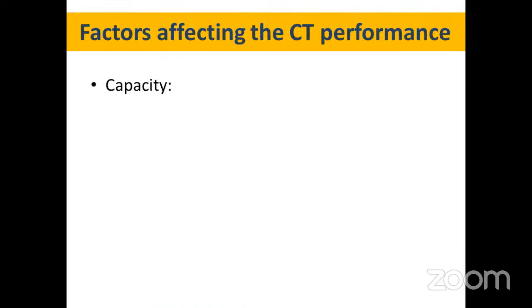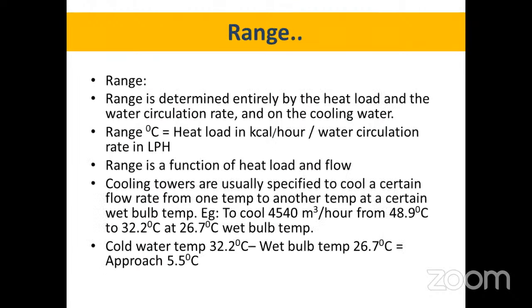Factors affecting capacity: the range. Range is determined entirely by the heat load. That is, the inlet and outlet temperature depend upon the heat load. The heat rejected in the condenser determines the range, along with the water circulation rate and the cooling water inlet temperature. Range in degrees centigrade is equal to heat load in kilocalorie per hour divided by water circulation rate in liters per hour. We'll be doing some problems, and we'll get an idea then. Range is a function of heat load and flow, as we have already seen.